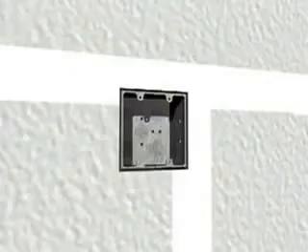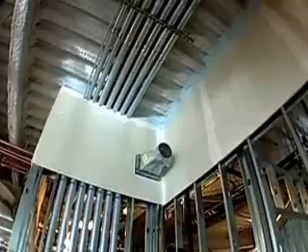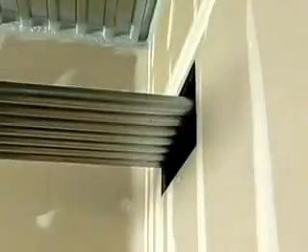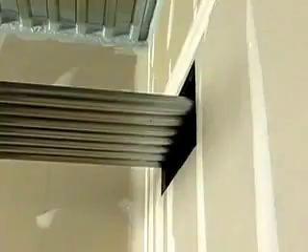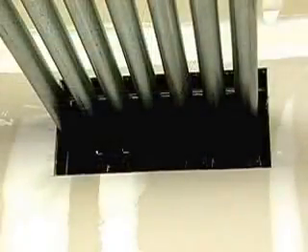Both through and membrane penetrations are examples of a single item being routed through one hole. Needless to say, grouped penetrations often share a single opening. A common example of this is where multiple conduits are racked together and routed through a large rectangular opening. This special condition can be sealed effectively, but requires care to ensure that the Firestop installation can handle the additional strain of such a large and complex opening.